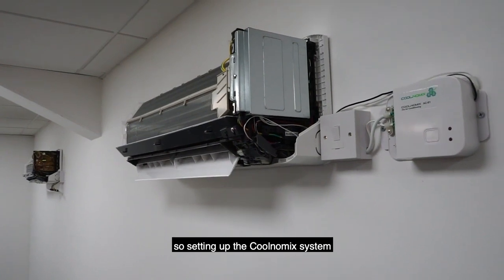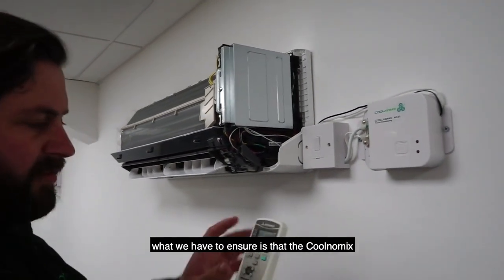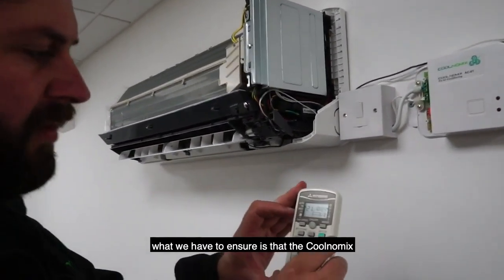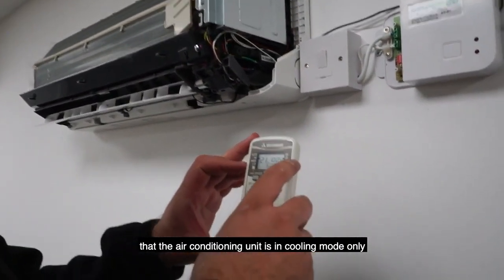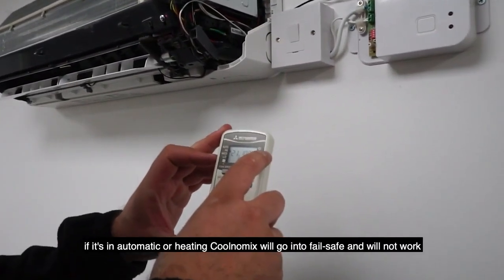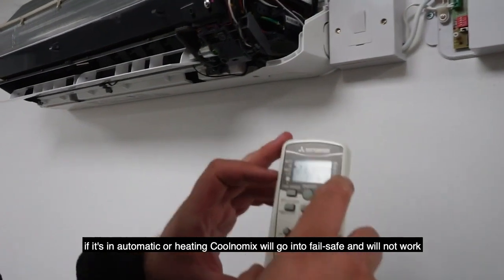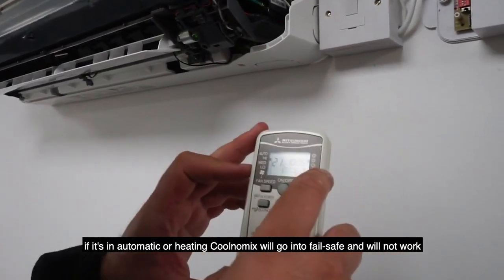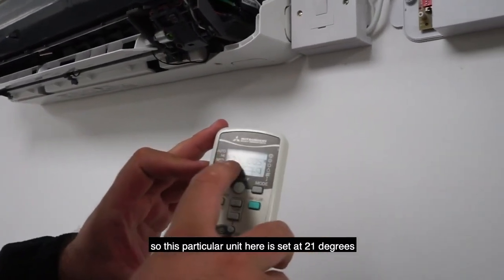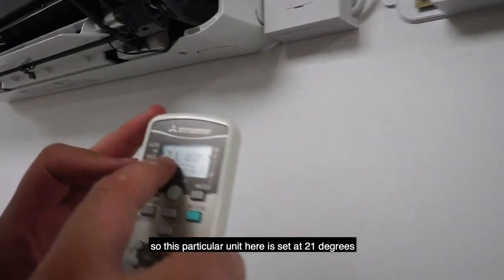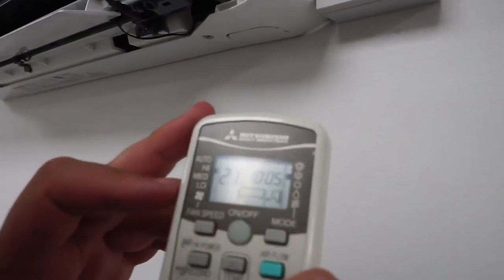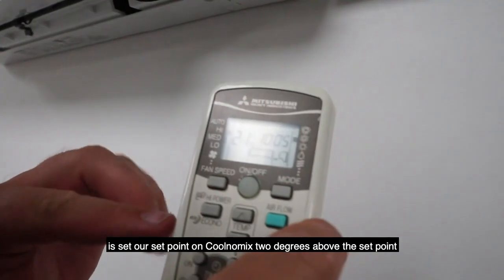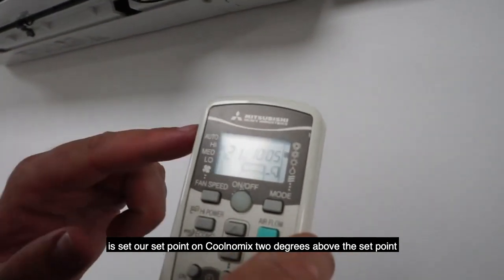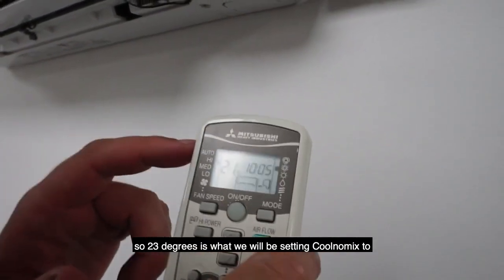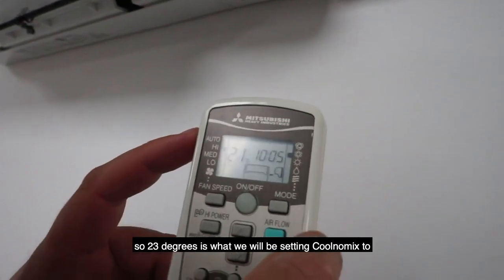So setting up the Coolnomix system, what we have to ensure is that the air conditioning unit is in cooling mode only. If it's in automatic or heating, Coolnomix will go into fail-safe and will not work. So this particular unit here is set at 21 degrees. What we're trying to do is set our set point on Coolnomix 2 degrees above this set point. So 23 degrees will be what we'll be setting Coolnomix to.